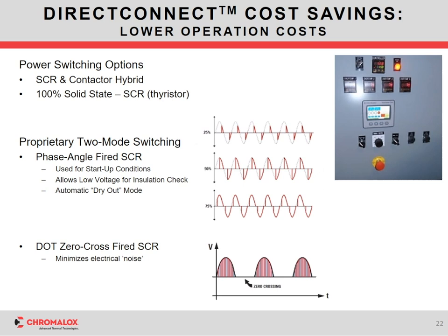We can control the electric power output into the heater in the same way, so that anywhere in the range from 0 to 100%, you're only applying the power that's needed for that process to heat it up. And in a DirectConnect system, there's two ways to provide power. There's a phase angle or zero cross. And depending on your application, the system can switch between those.